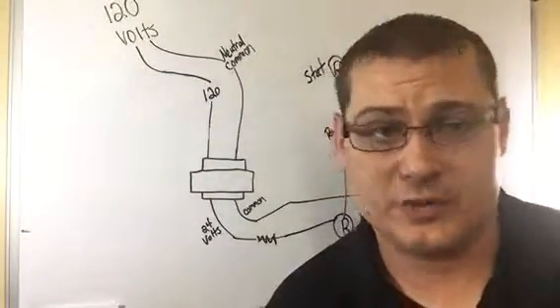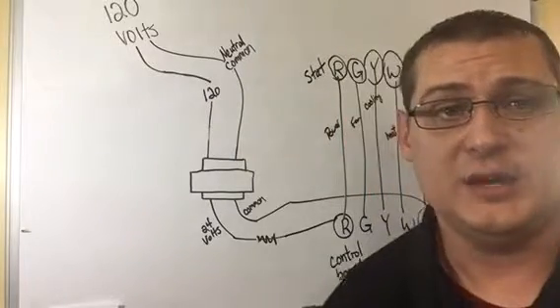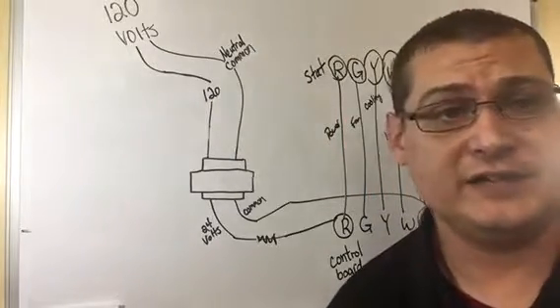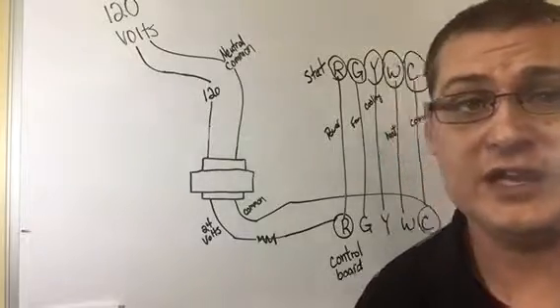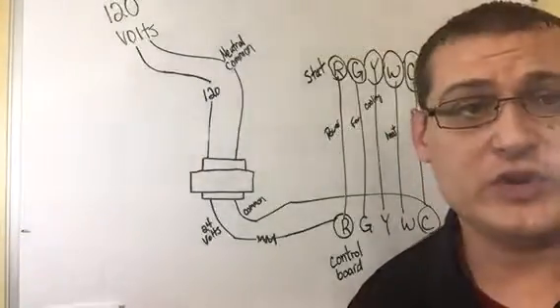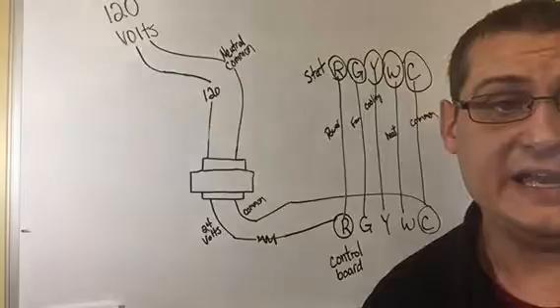R is your power, your 24 volts. G is your fan. That's the switch for the fan. Y is for cooling. W is for heat. And C is common.